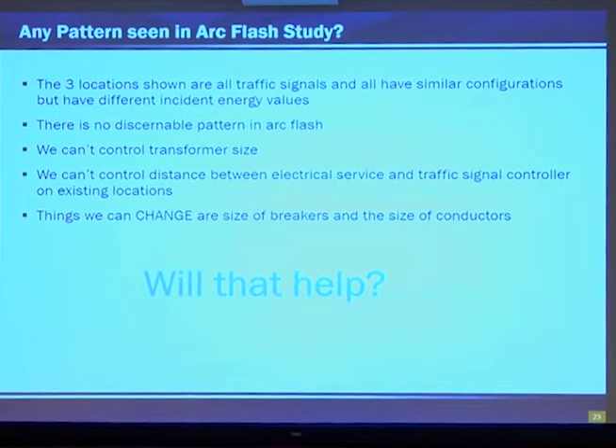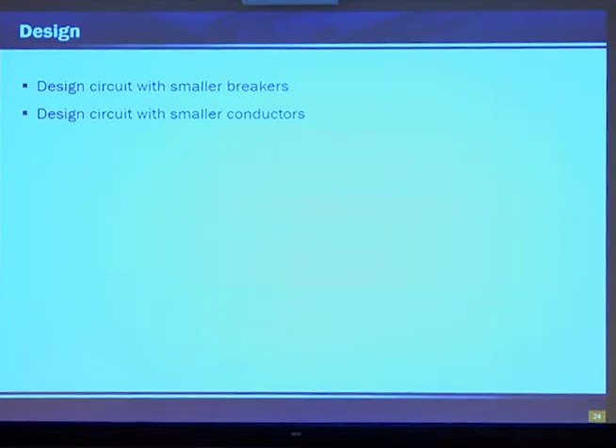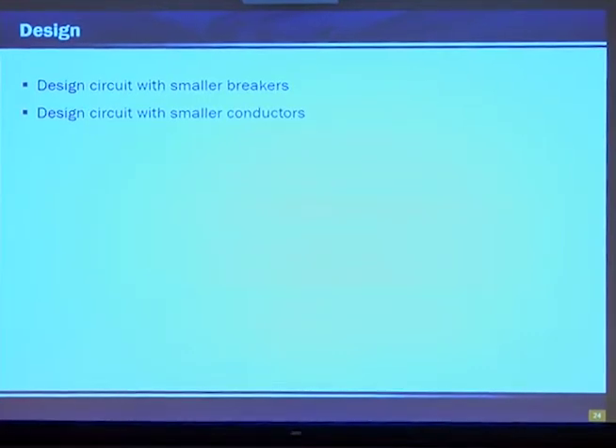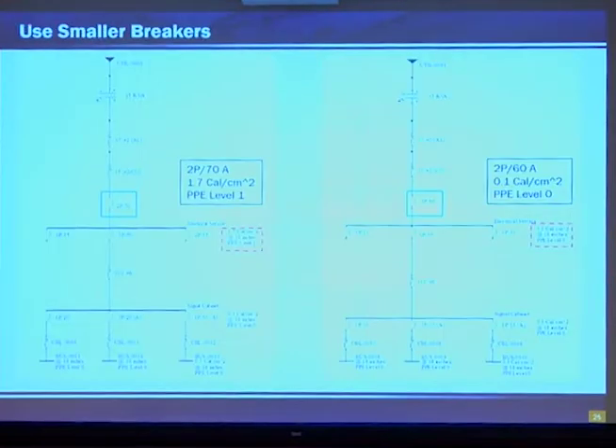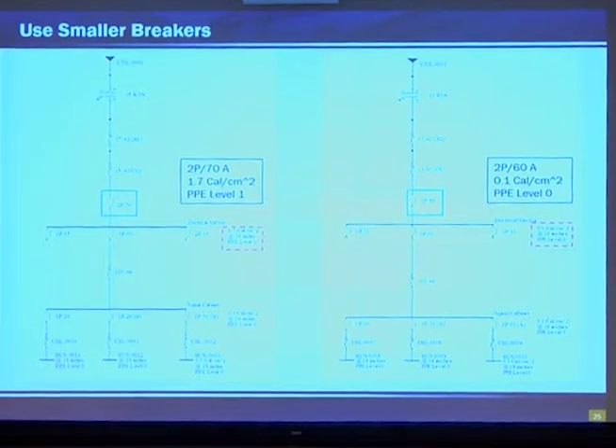But will that actually help? So from a design perspective, we started doing research and trying to run calculations on actually doing designs using these theories, reducing the breaker sizes and the conductor sizes. So I wanted to show you a couple of these examples. Using smaller breakers. So we took a traffic signal, and we normally run a 2-pole 70 breaker for the traffic signals. And the incident energy was 1.7 calories per centimeter squared, and we reduced it to a 2-pole 60. And the incident energy we found went from 1.7 calories per centimeter squared to 0.1 calories per centimeter squared at the service, reducing the PPE level from a 1 to a 0.